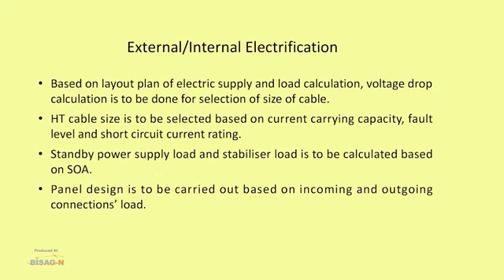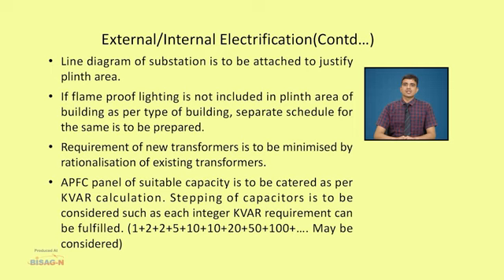Based on layout plan of electric supply and load calculation, voltage drop calculation is to be done for selection of size of cable. HT cable size is to be selected based on current carrying capacity, fault level and short circuit current rating. Standby power supply load and stabilizer load is to be calculated based on scale of accommodation. Panel design is to be carried out based on incoming and outgoing connections load. Line diagram of substation is to be attached to justify plinth area. If flame proof lighting is not included in plinth area of building, as per type of building, separate schedule for the same is to be prepared.